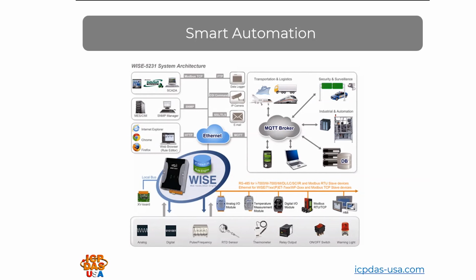Smart automation allows for implementing control and monitoring applications without programming. You just set up the conditions you want through a web page, so you can set up the turning on of a light at a certain time or the turning on of an air conditioner based on temperature measurements. Some air conditioners communicate over infrared, for example, and we have infrared to Modbus gateways, so you'd be able to use this. The one on the screen here is WISE 5231, and it supports Modbus. So with that gateway, it allows you to communicate with your infrared air conditioner.